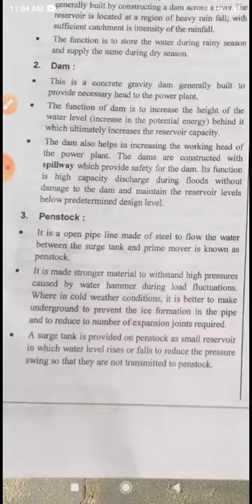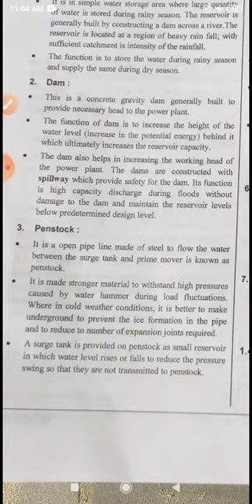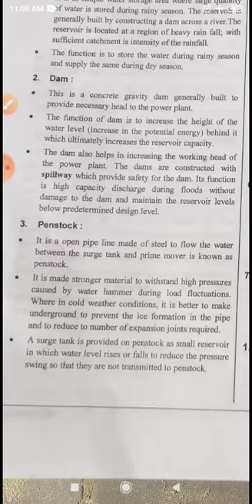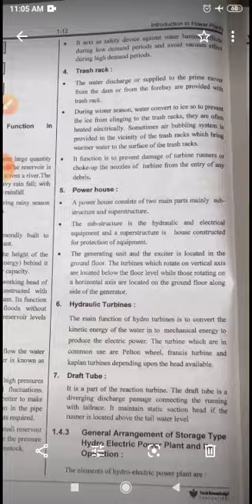Penstock. It is an open pipeline made of steel to flow the water between the surge tank and the prime mover, known as the penstock. It is made of stronger material to withstand high pressure caused by water hammer during load fluctuation. In cold weather conditions it is better to make it underground to prevent ice formation in the pipe and to reduce the number of expansion joints required. A surge tank is provided on the penstock as a small reservoir in which the water level rises or falls to reduce the pressure swing so that it is not transmitted to the penstock. It acts as a safety device against water hammer effect during low demand periods and avoids vacuum effect during high demand periods.